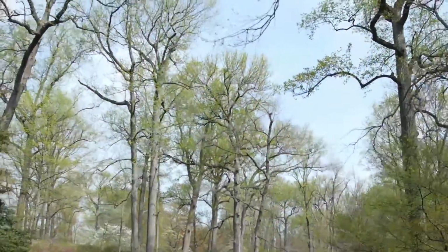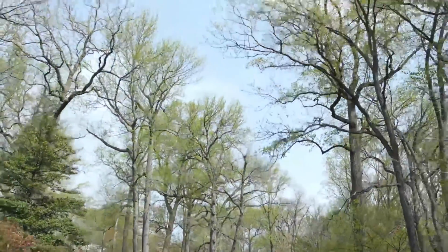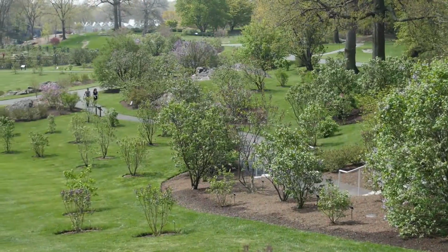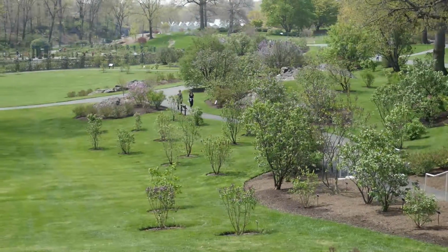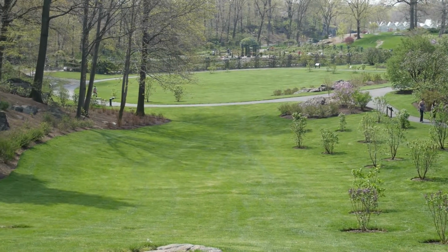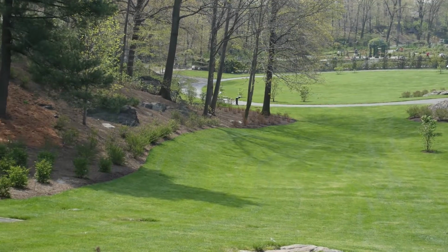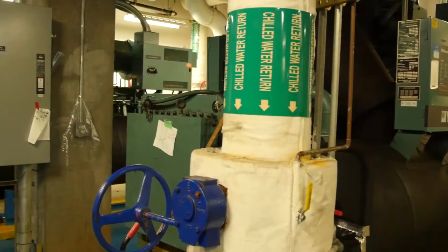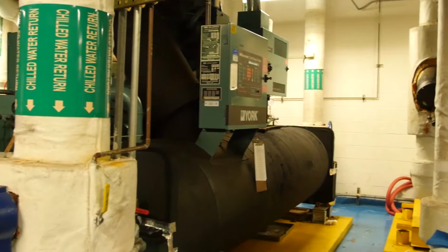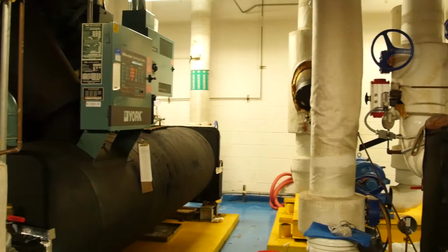We contacted Permafrost. We told them that we were interested. We got all the data together that was necessary, and we applied to the Excel program to see if we could utilize this and get the unit charged with the Permafrost and show a payback period that was reasonable for the installation. The procedure that we used was kind of unique because Permafrost is not a construction project, it's an oil additive installation. So even though it seems like it's expensive for the size of the container, which was about 1 gallon per each unit, maybe 1.5 gallons per each unit, we have a 300-ton chiller.